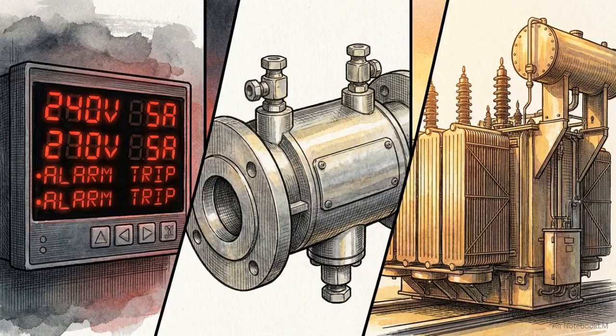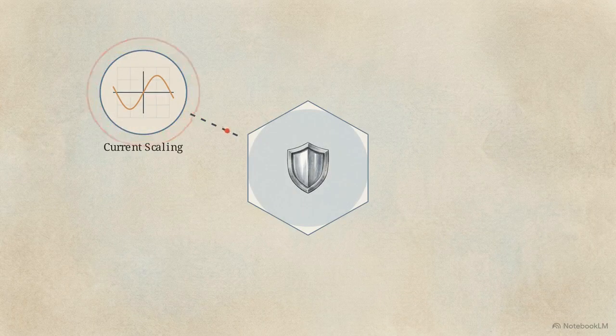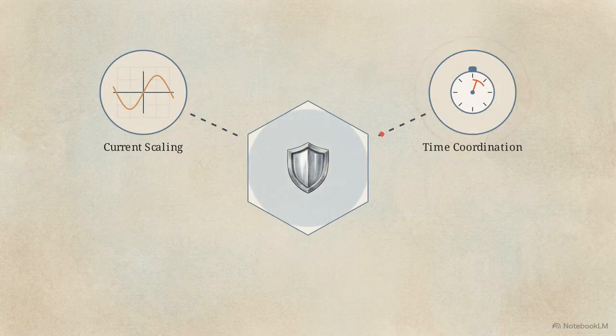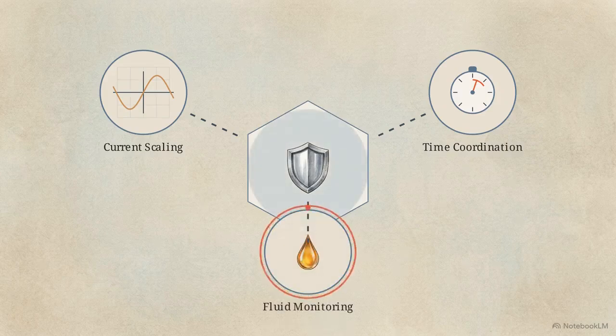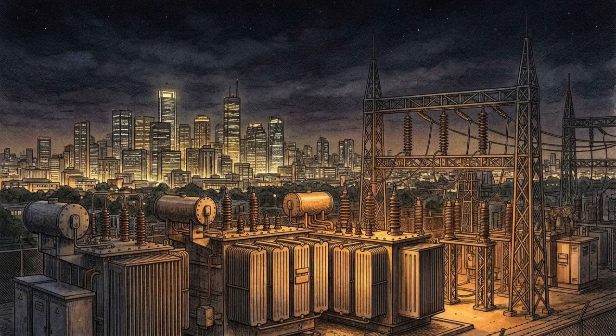The security of the grid relies on these layered systems working together in fractions of a second: the precise scaling of current transformers, the strategic coordination of time delays, and the physical failsafes monitoring fluid dynamics. Effective transformer protection integrates electrical mathematics and fluid dynamics to detect high current faults and incipient chemical breakdown, ensuring the continued stability of the power network.